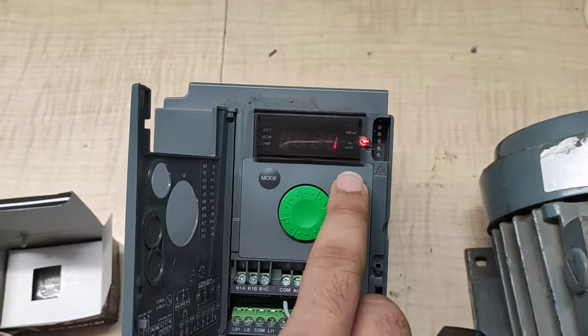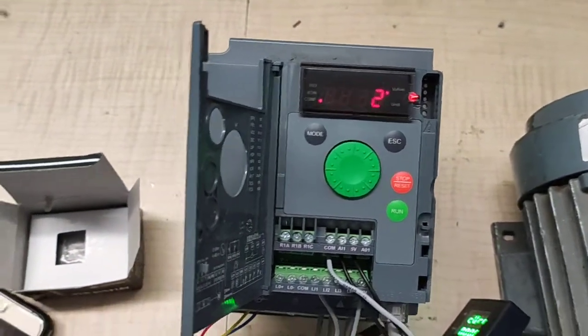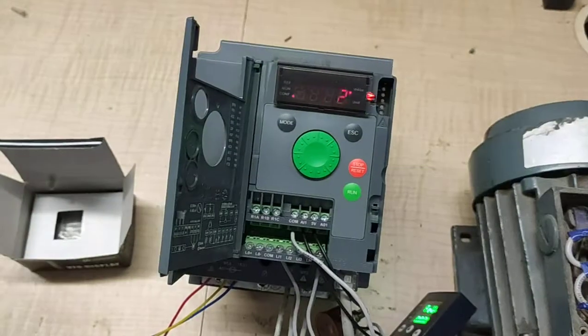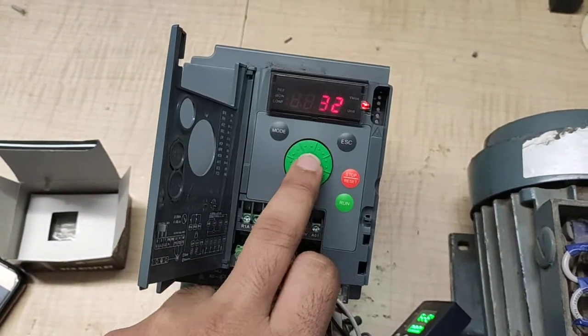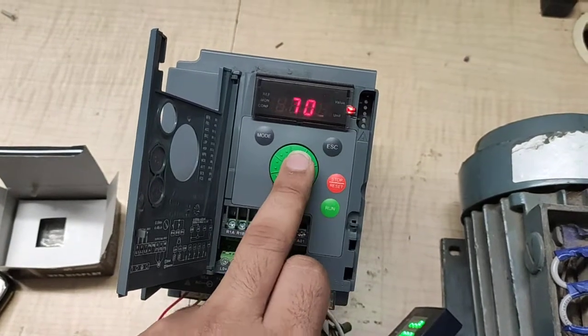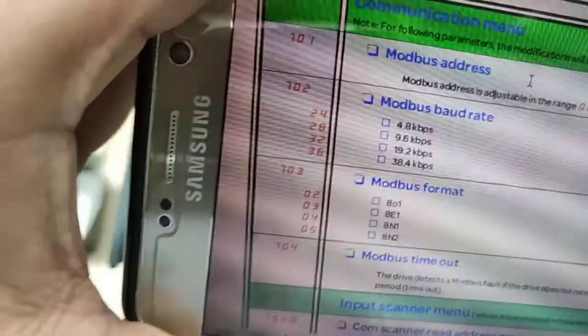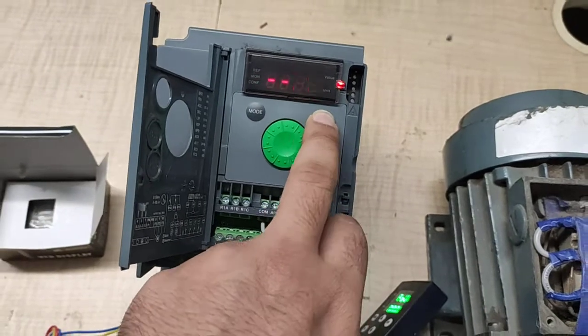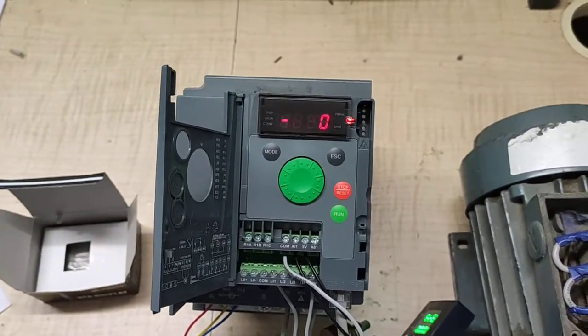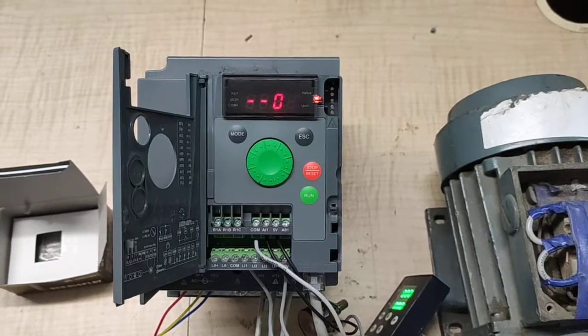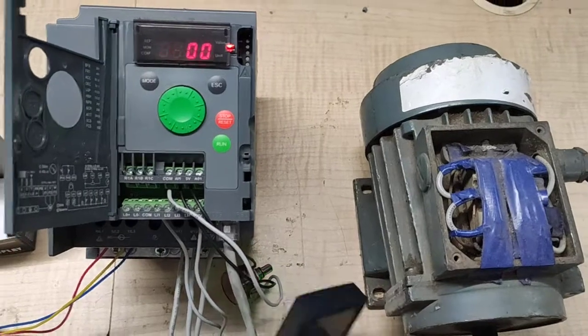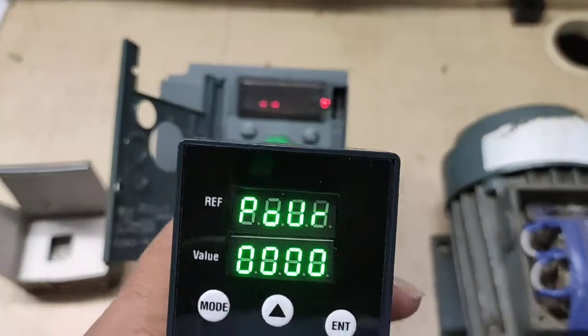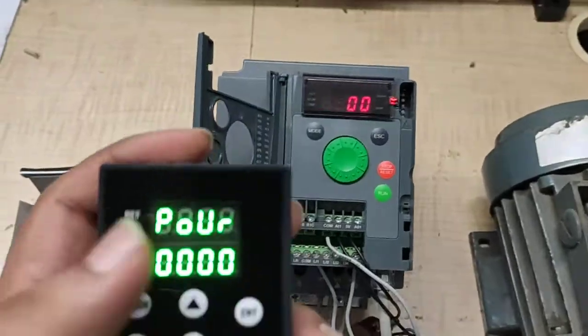Parameter 701 is already set to 1. Parameter 702 is 32 for 19.2 kbps, and parameter 703 is 34 for Modbus format 8N1. After setting this up, exit the menu and perform a power on/off cycle. Our Modbus is now set and we will go to auto mode.